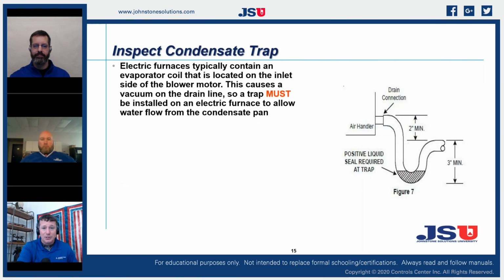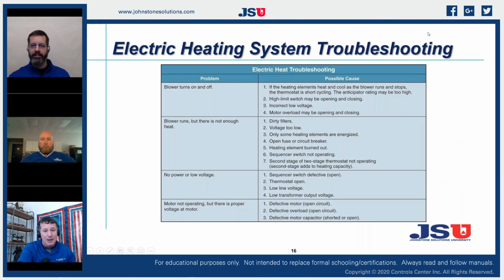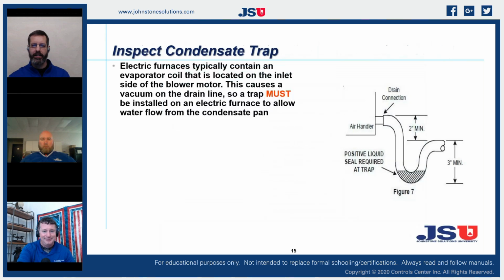And it's always good to make sure that we're checking our condensate traps as a routine, as we're there checking out our electric furnace. It's good to see what's going on inside of our traps as well, and to make sure that we're using the proper type of trap, because we're now pulling against our blower. Can I make a comment on that quick? Oh, yeah. As it says there, anything on a negative side of a blower needs to be trapped. Those measurements are actually more important than people think. So people think as long as it's got the little P trap U in it, no big deal. We can put it in a running trap.